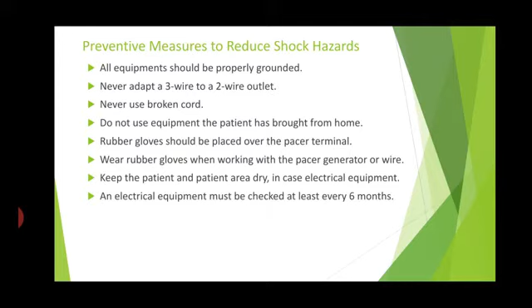Next one, rubber gloves should be placed over the pacer terminal. Wear rubber gloves when working with the pacer, generator or a wire. Next one, keep the patient and patient area dry in case of electrical equipment. And electrical equipment must be checked at least every 6 months.